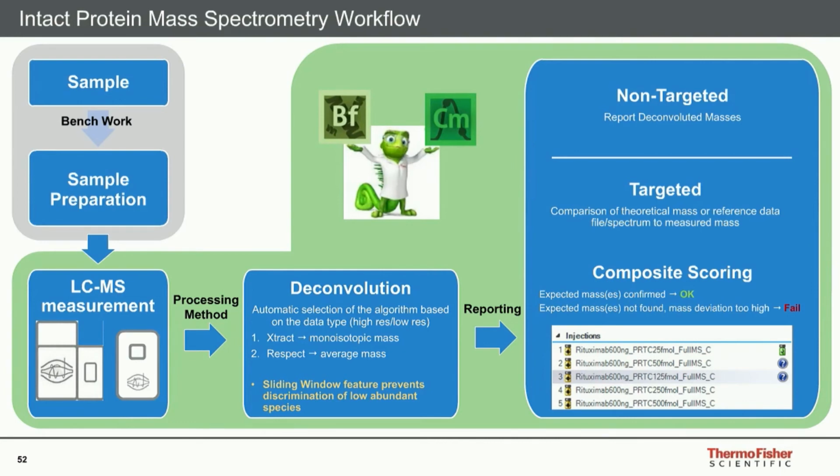However, if you know already what to expect, you would like to confirm certain variants, you would like to see that it's the same peaks and masses you've already analyzed in a previous analysis, you could choose the targeted approach. You choose the masses you expect, and then the software will try to match all the masses from your new sample with the mass table that you provided.